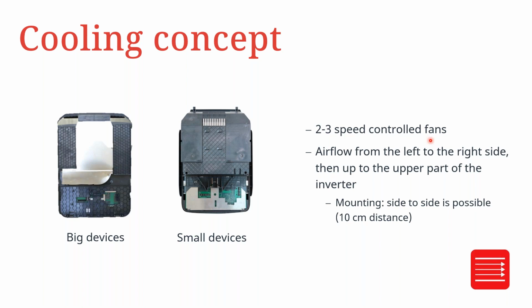The cooling concept of the Fronius Snap inverters is also something that needs to be understood when you're installing the inverters. As we know, all Fronius inverters are actively cooled, and this means they employ 2 to 3 temperature controlled fans, and therefore, depending on the type of inverter, air is coming from either the left or the right side or from both sides of the inverter, and then hot air is escaping from the top of the inverter through provided slots. So at the back, you have a heatsink that is in contact with the electronics inside. So the cooling air never gets into the electronics component. It's just basically flowing over the heatsink, and the heatsink is taking the heat away from the electronics inside the inverter.